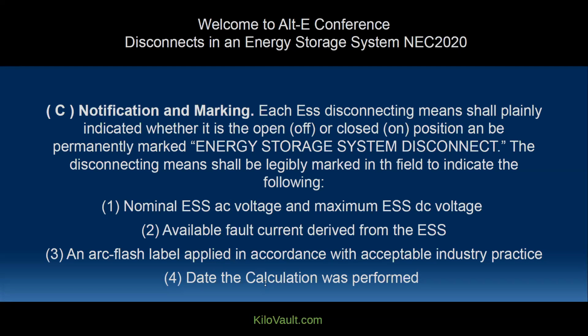Theoretically, I don't see that. You would just need a disconnect in between, say, that's probably readily accessible. I can't point to where that would be in the code, or say your AC. That's what I'm saying. Talk to your local inspector at this point, and see what he'll actually approve. If you don't have an inspector coming to check on things, I really wouldn't worry about it. The systems nowadays, as long as you're installing a system with AC/DC switch gear, proper size conductors, overcurrent protection, ground fault and arc fault protection, then you're going to be well safe enough at that point. Monitor your system, quality work. You shouldn't have an issue at that point.